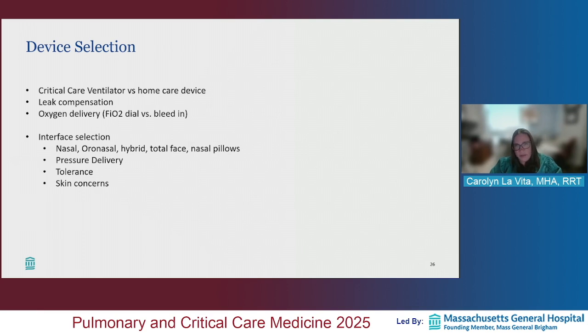In a home care type ventilator, there is no dial for oxygen. So what we have to do, with a couple of different adapters and contraptions, is bleed in oxygen from a flow meter on the wall. This is a very similar principle to the high flow pictures that I showed you earlier: if the flow through the circuit is higher and the oxygen bleed-in is fixed, your net FiO2 is going to be lower. So with the way the flow is in these home care devices, even if you have the flow meter set all the way up in an acute situation, the highest FiO2 you're going to get is somewhere around 0.4. So you do have to be mindful of that, and select the right device to make sure that you are treating the patient most appropriately.